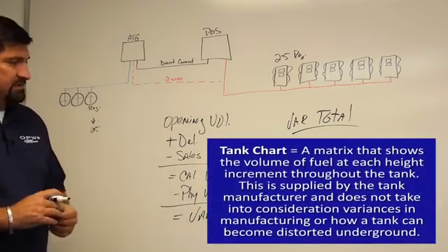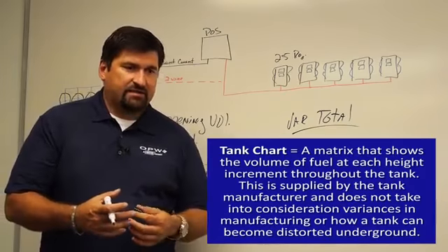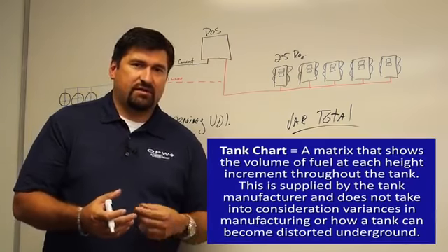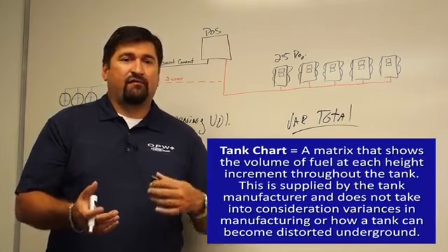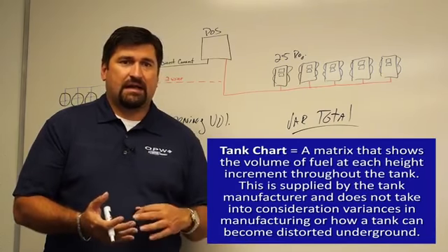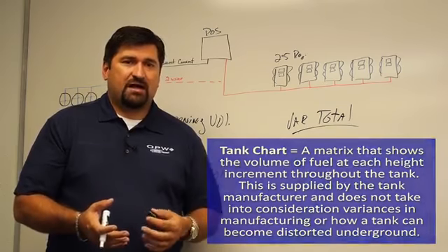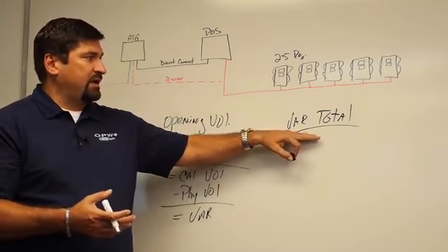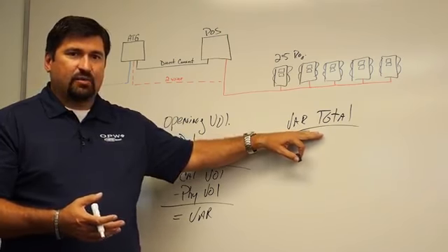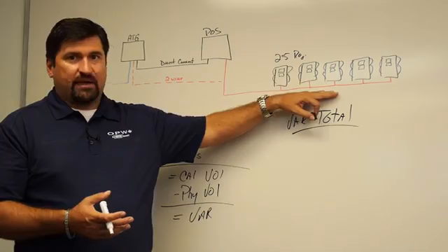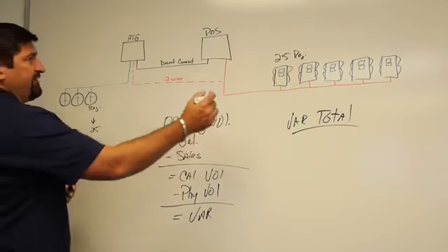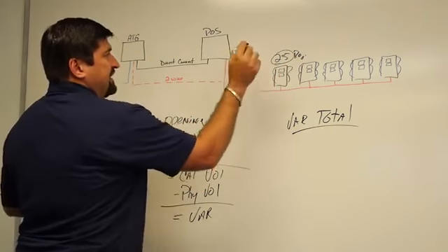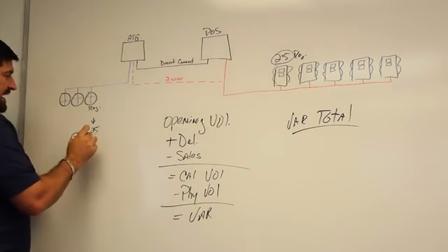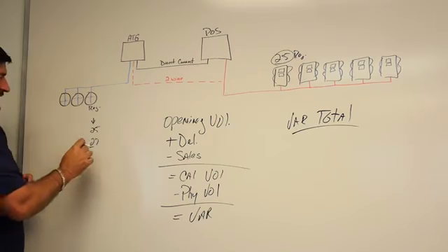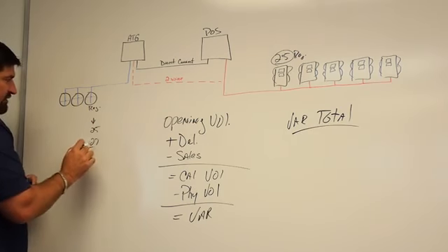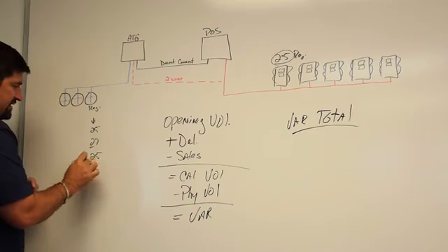The other thing is that when you start looking at variances within the tank, most tank charts are either plus or minus 5% inaccurate from the manufacturer themselves, whether it be fiberglass or steel. They try to get as close as possible, but during a period, you can actually get the gauge to recalibrate the tank by using calibrated meters from the dispenser. If I see within the first 50 days 25 gallons leaving the dispenser and I see 27 gallons leaving the tank, I will go ahead and change the end shape or the factor in that tank to make sure that it's 25 gallons.